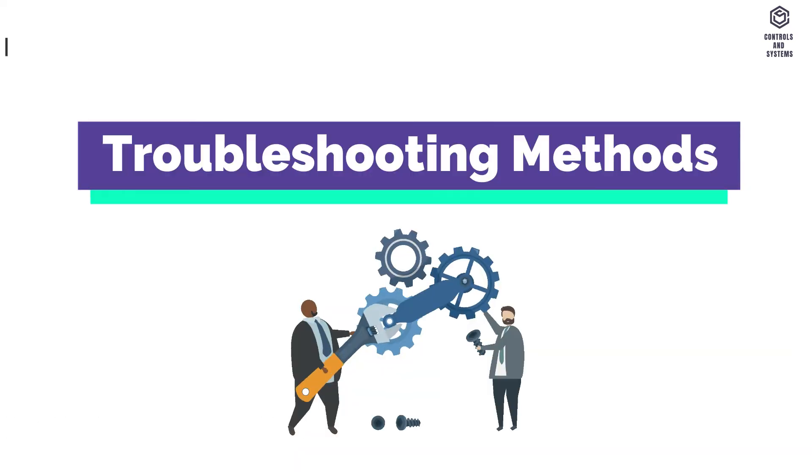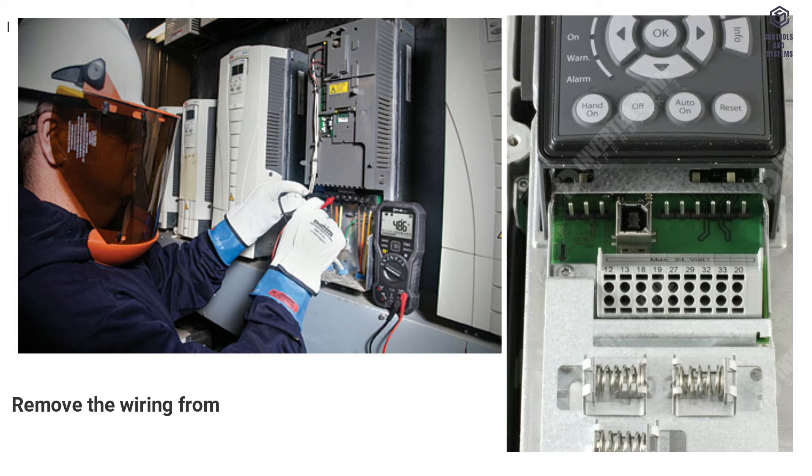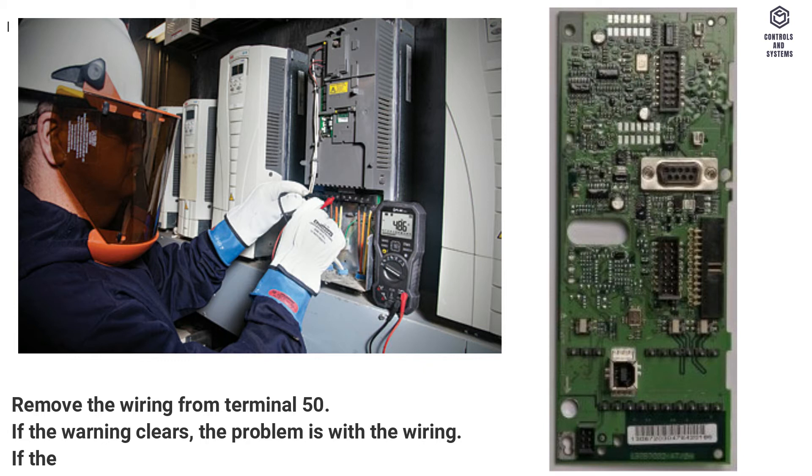Troubleshooting methods: Remove the wiring from Terminal 50. If the warning clears, the problem is with the wiring. If the warning does not clear, replace the control card.